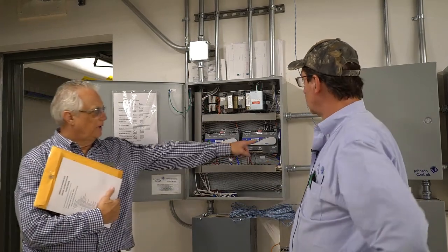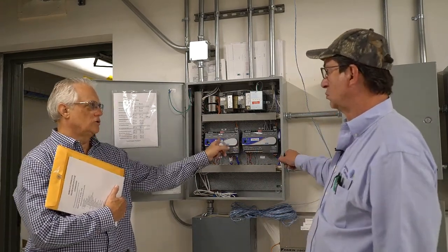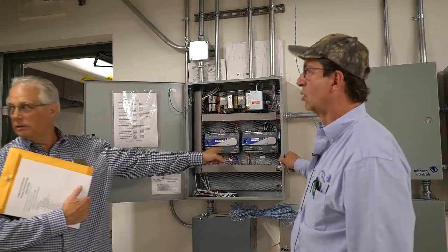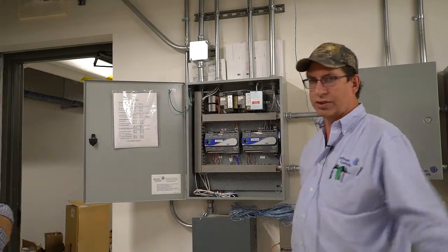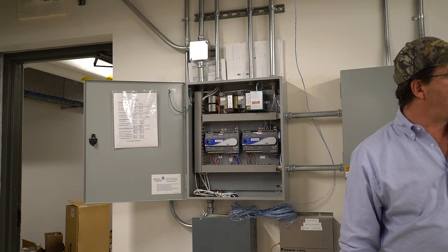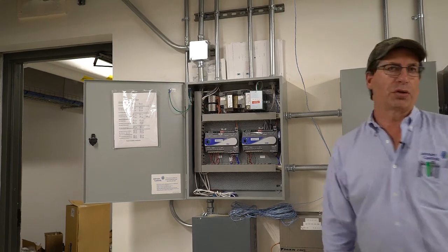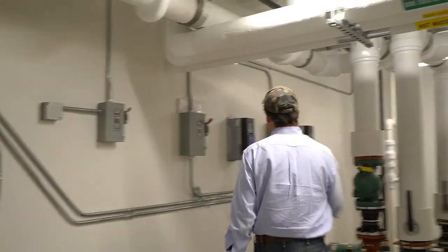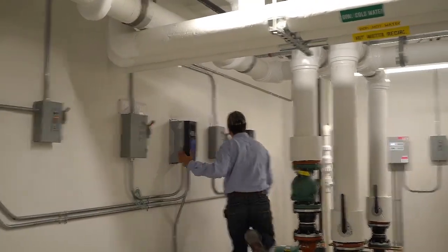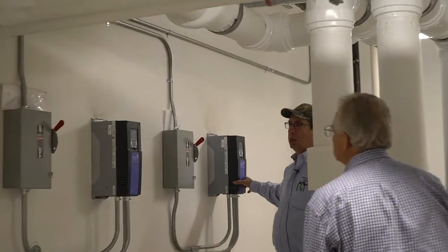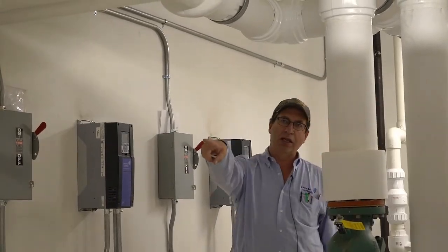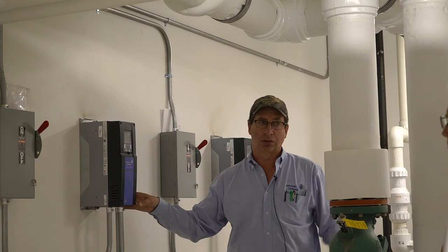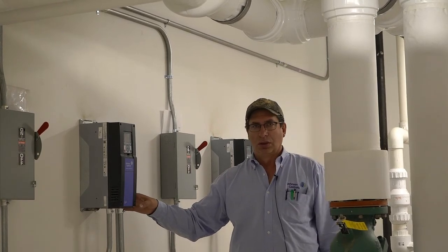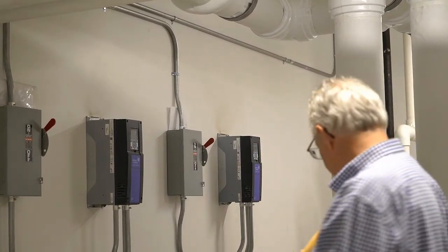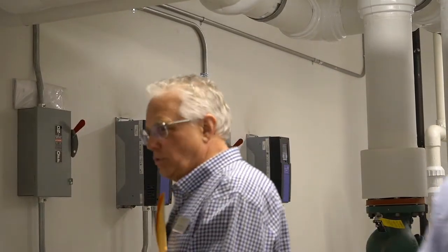So this is telling the VFDs what speed to run at, but the calculations for what speed to run at are coming out of the FEC. Correct. And it's the same thing with our VFDs over here. They are also connected. So you've got the pump VFDs here and here. These are also connected back to that heating controller through the SA bus. So we're able to pull in a lot more points that way. So we can look at amperage loads. Correct. Correct.